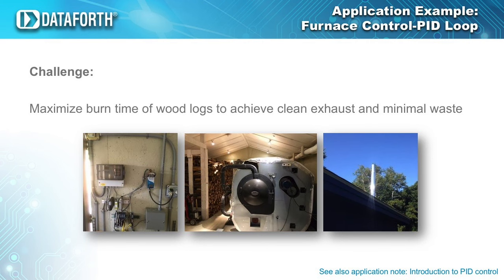The first example is a little bit of a hidden gem because the application is housed in a private residence. The homeowner's goal was to create a PID system which maximizes the time each wood log burns and at the same time minimizes any waste, aiming for maximum efficiency. In applications like this one, a PID controller is ideal. As you may know, PID controllers are used in many automatic process control applications. They can regulate flow, temperature, pressure, level, and many other industrial process variables. Without automatic and continuously modulated control, all regulation tasks have to be done manually.